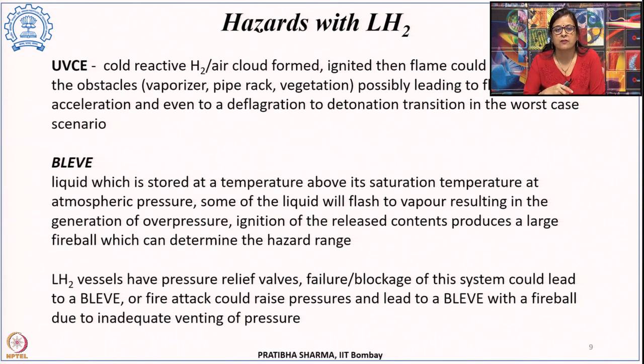Now, the liquid hydrogen vessels, usually they are equipped with pressure relief valves. However, at times because of the failure or blockage of these pressure relief valves, such type of incidents can happen. Or even there could be a fire attack from a nearby site that could increase the pressure inside the liquid hydrogen vessel, and that could lead to BLEVE. And with a fireball being formed, this could be due to inadequate venting of the pressure in the liquid hydrogen vessel.